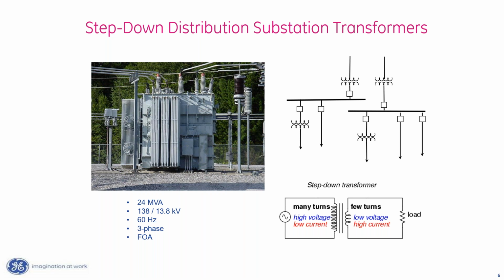So what that does for us is that the delta side of the step-down transformer is wired on the high voltage side of the transformer, the transmission side. And the Y connection is wired on the distribution side at 12.47 kV or the medium voltage level. So that Y connection, typically on both of these, the step-down and the GSU, is typically grounded either solidly or impedance grounded in some way, and that gives us enough ground fault current that we can sense the ground faults and we can coordinate with it.